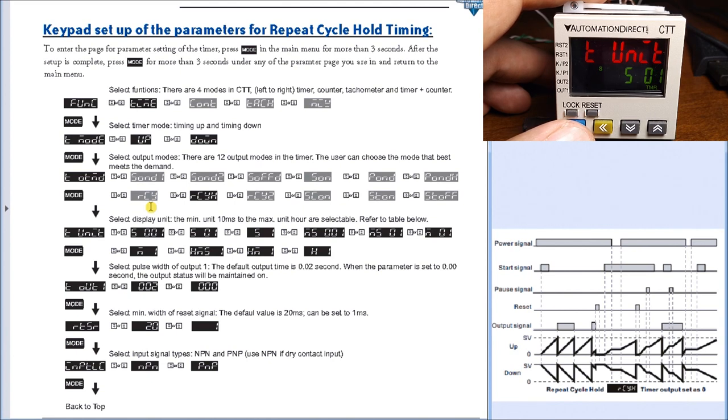Mode key again - this specifies our timing units. In our case we have 0.1 second. Our output is set for 0.00 which will maintain outputs so we see the output signal go on for a duration, off for a duration. Our reset is at 20 milliseconds and our input type is PNP, which goes back to the wiring. Hit it once more and it loops back to the beginning of our setup menu.